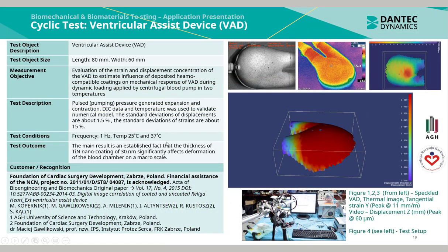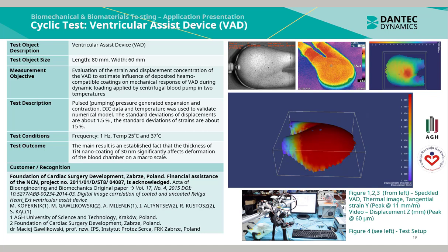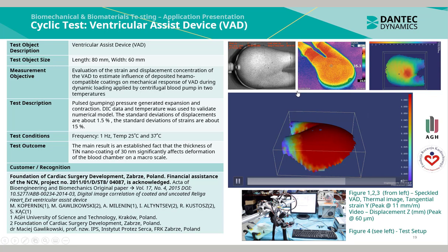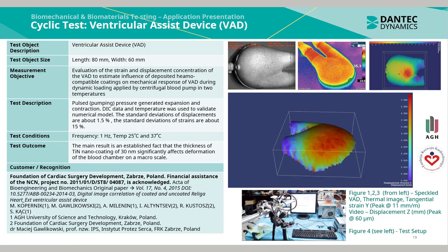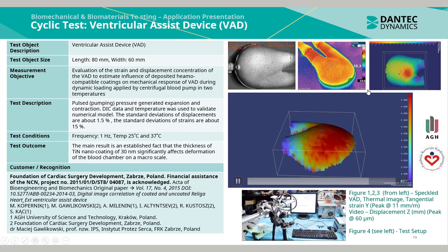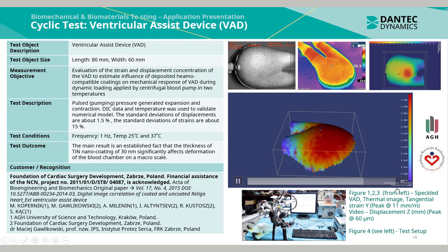This is a cyclic test of a ventricular assist device or VAD. The test object size is approximately 80 mm by 60 mm, and can be seen here in the speckled image of the camera acquisition measurement. Here is an infrared camera picture of the VAD in operation, with the visualization result showing the peak Z displacement at 60 micrometers.